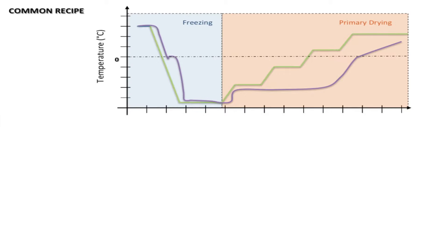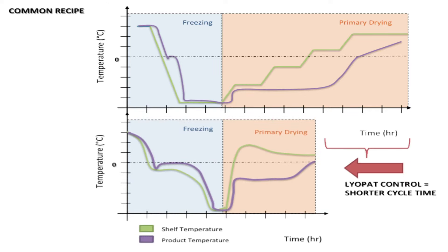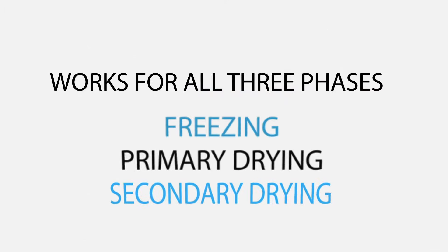Up until now, freeze drying cycles have been controlled by shelf temperature. With LyoPAT, ice crystal growth during the freezing process is monitored and controlled based on heat flow. Primary drying is then controlled by product temperature without the use of thermocouples. LyoPAT works for all three phases of the freeze drying process including freezing, primary drying and secondary drying.